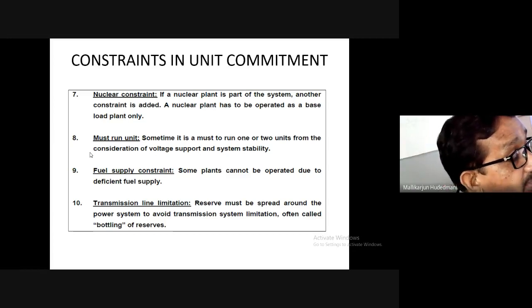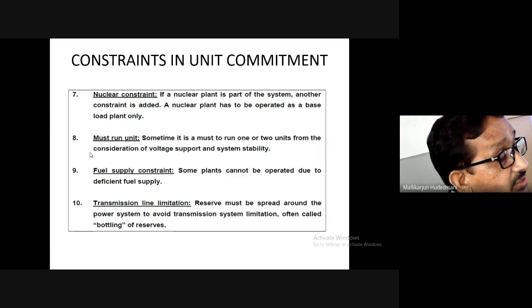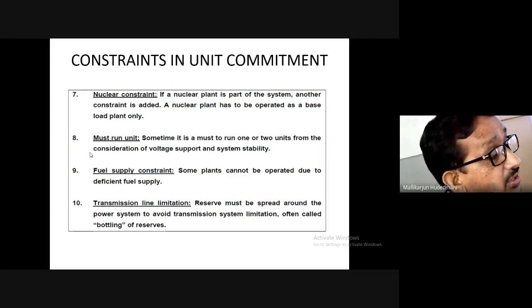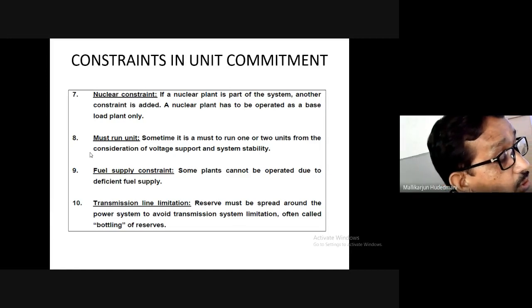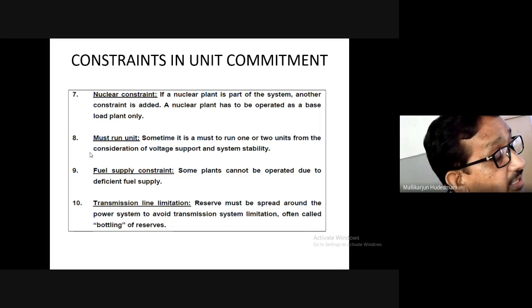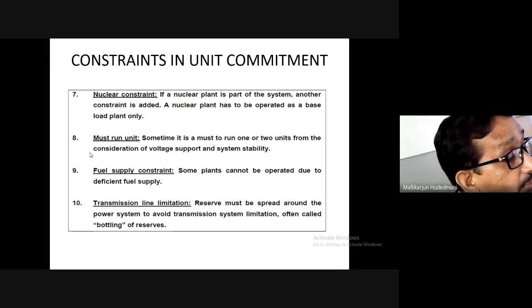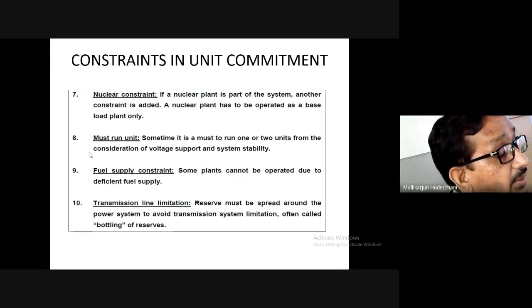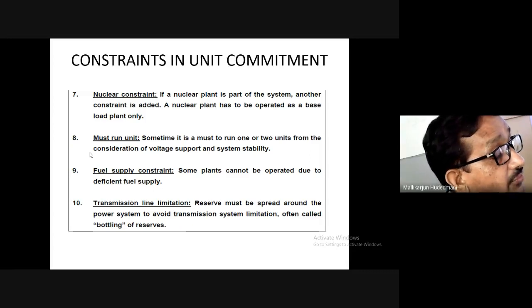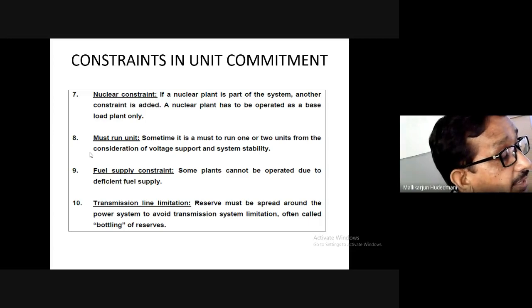It is important to keep in view that this generator being put into force is kept under observation for economy as well as voltage support. Voltage support is needed because any inductive or reactive power requirement changes in the power system definitely adversely affect the voltage. If you in turn try to adjust the voltage, the active power delivery definitely gets affected.